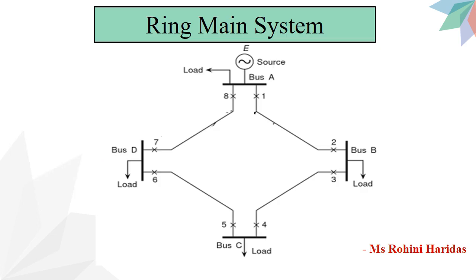Here the figure shows the single line diagram of a typical ring-main system. In this system, various power stations or substations are interconnected by alternate routes, thus forming a closed ring. In case of damage to any section of the ring, that section may be disconnected for repairs and power will be supplied from both ends of the ring, thereby maintaining the continuity of supply.